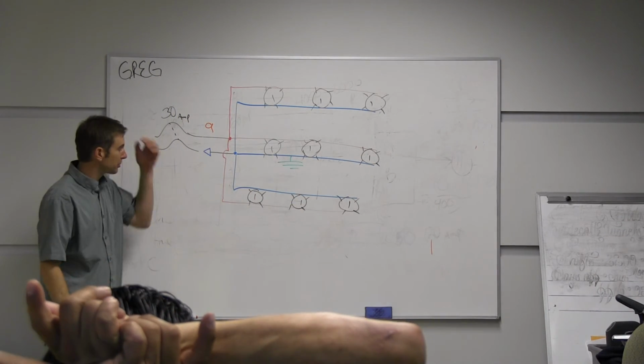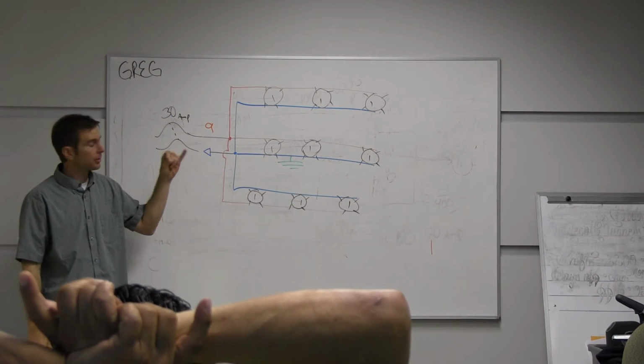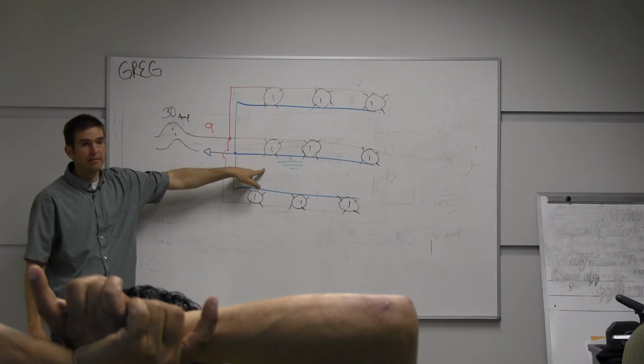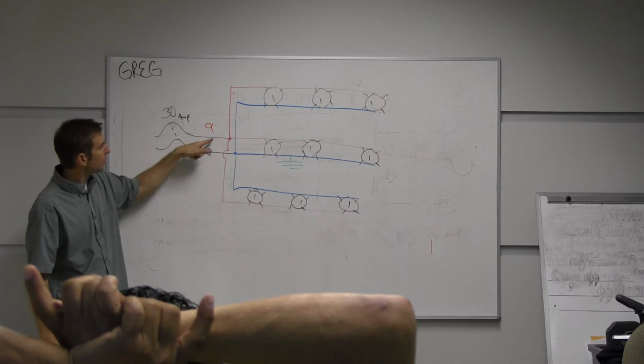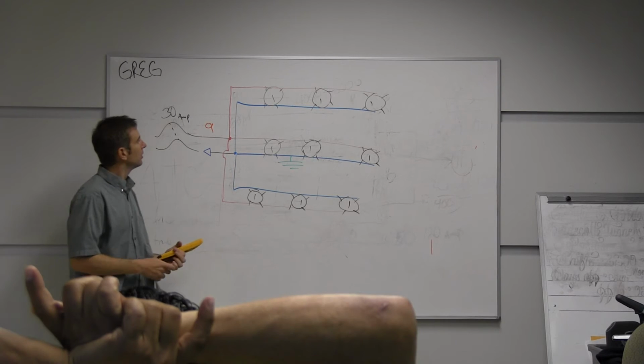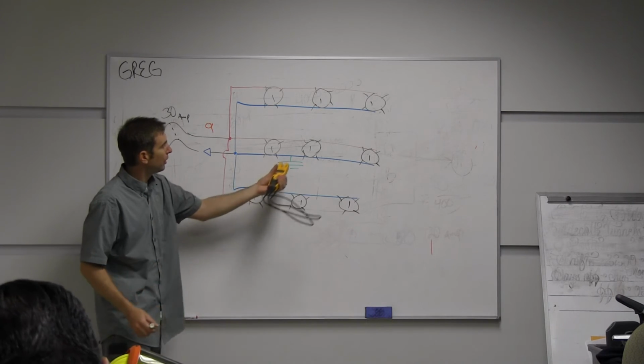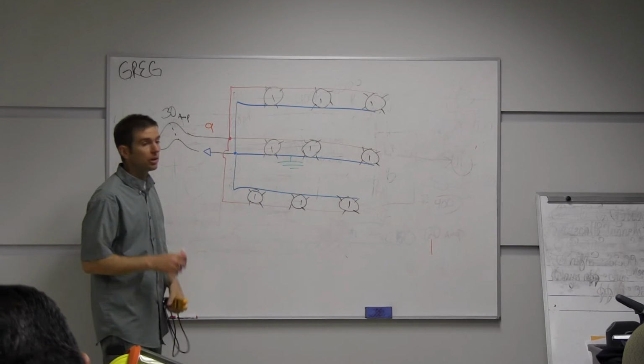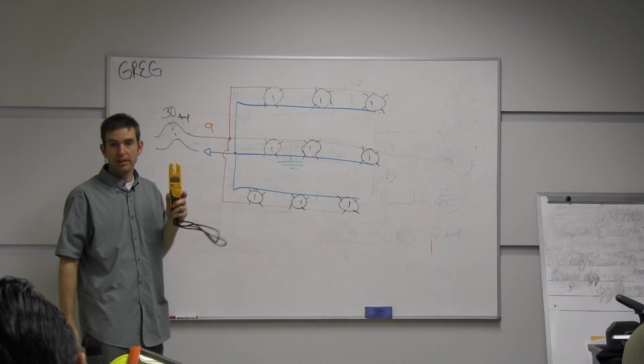So how does this help us with troubleshooting? We've identified what wire it is. We've identified what the problem is. We have a ground fault. We just don't know where it is. We have 9 amps here. So we know we're going to have 9 amps here. We're looking for 9 amps with our amp probe.